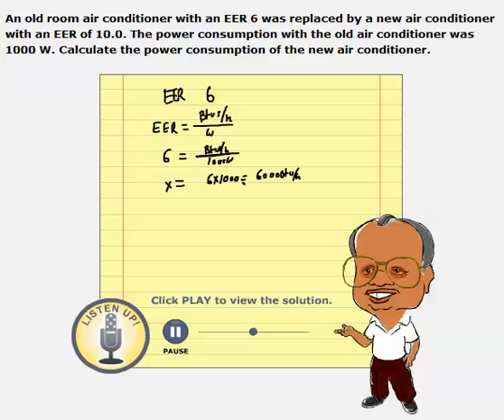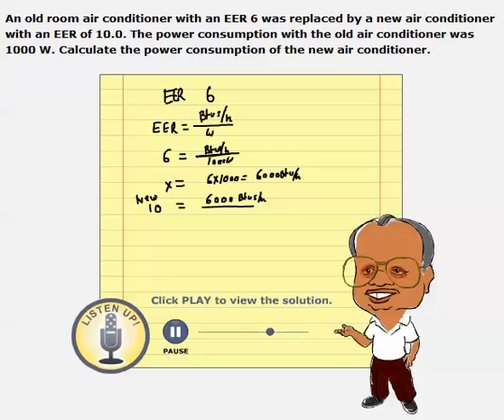The room size is not changing, but we are just replacing the old air conditioner with a new one. The new air conditioner has an EER of 10, and it is still pulling 6,000 BTUs per hour out. How many watts of power does the new one consume?